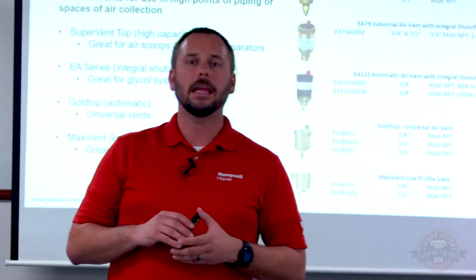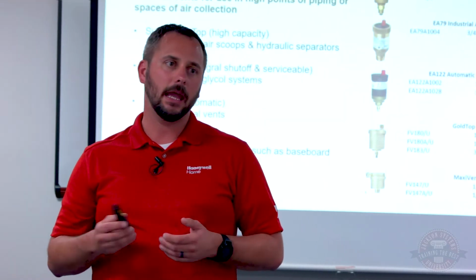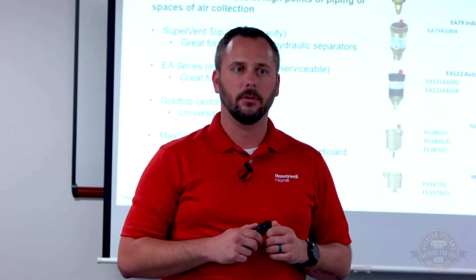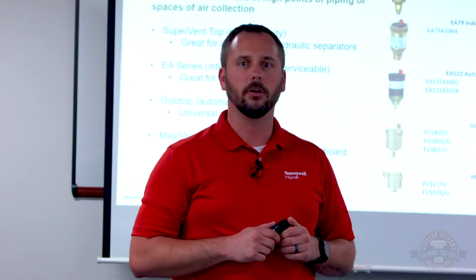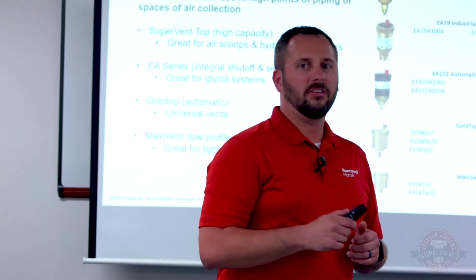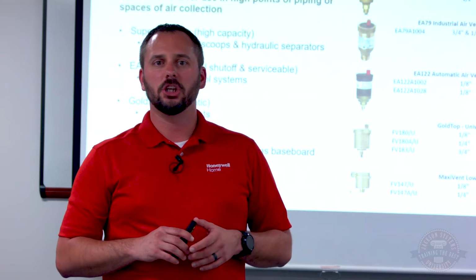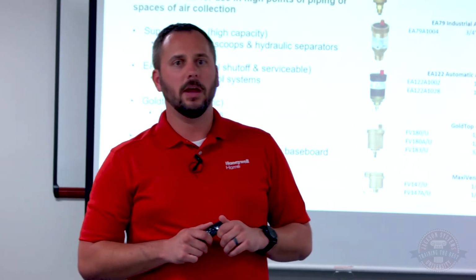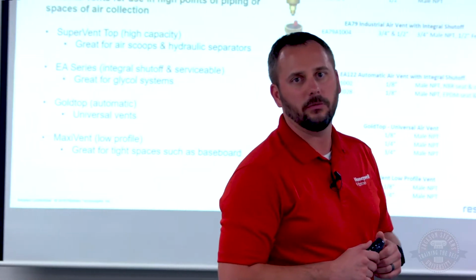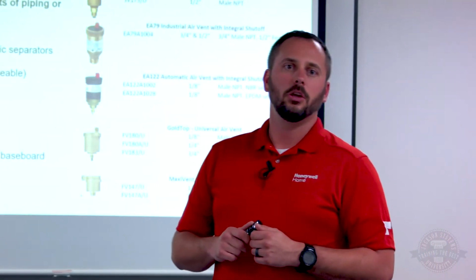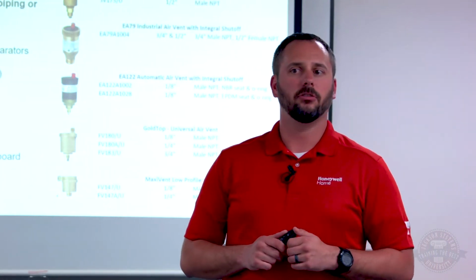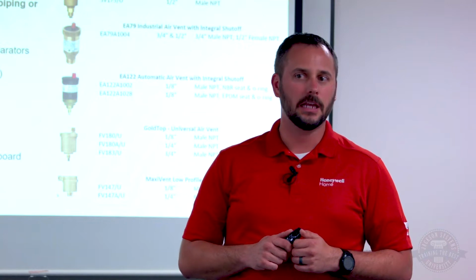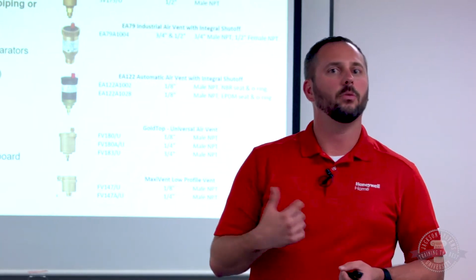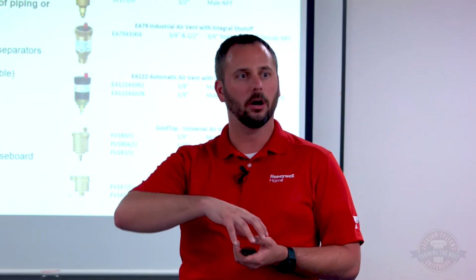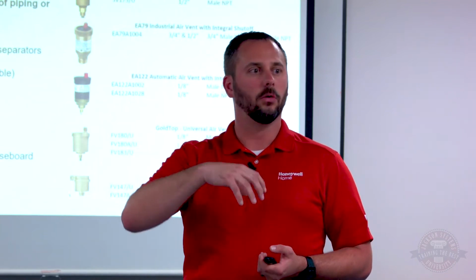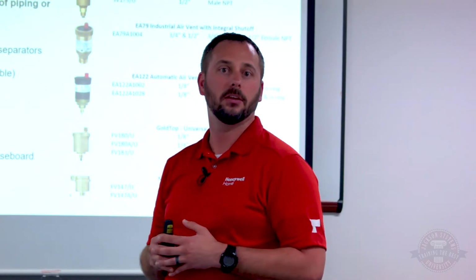We also have an EA series vent. So the EA is a pretty unique vent that we do quite a bit with in certain areas of the country. What makes the EA unique is it has a built-in shutoff valve. So if you have an area where you are having constant failures on air vents, you can put this in and actually shut it off to prevent leaking. When you shut it off, it's actually rebuildable as well. So you can take the top apart, come in with a new one, and replace the whole float assembly without having to drain down any of the system at all.